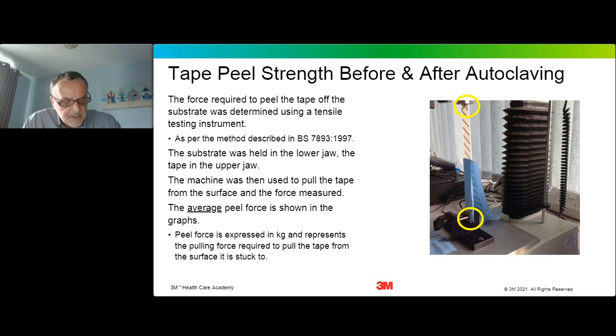The tensile testing machine was then activated, and it slowly started to pull the two parts of this assembly apart. And whilst it was pulling them apart, it was measuring the force that was required to pull the tape from the surface of the wrapping material. Now, this force can be expressed in different ways, but for the purposes of simplicity, in these tests, it was expressed as the equivalent kilogram weight that would be required to peel that tape from the surface.